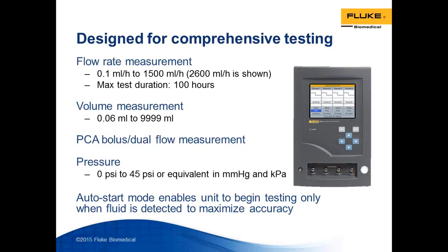The ID5 also has PCA and dual flow measurement, so that's different from the low-end analyzer. It has pressure measurement of 0 to 45 psi as well. Both the ID5 and ID1 have a unique feature called Auto Start. Auto Start is a mode which only begins testing when fluid is detected, which gives you time to start the pump, but the ID5 or ID1 are not going to start taking those calculations until they detect fluid.